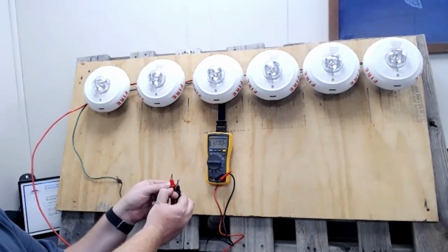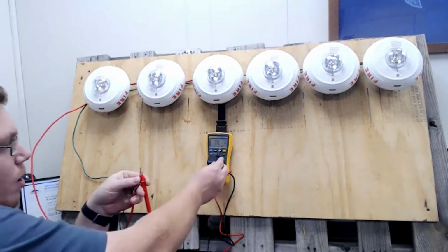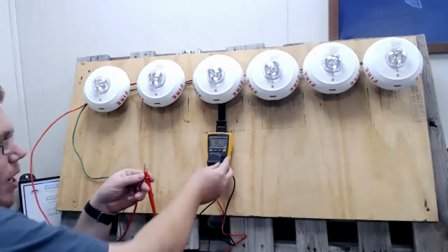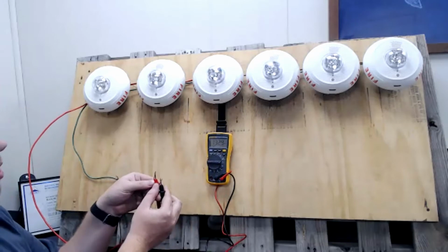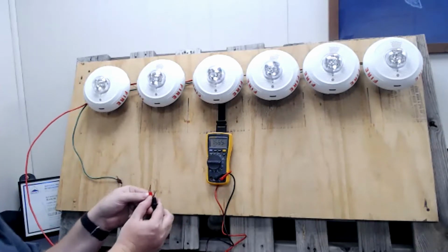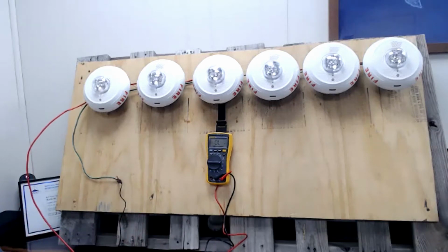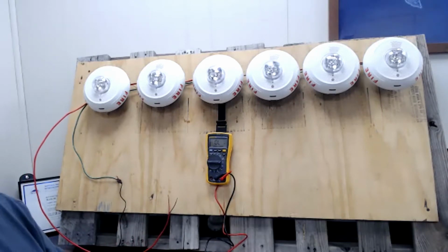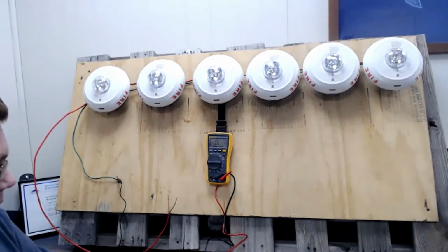So right here, looking at these, I'm bouncing around between 1.2 and 1.3 mega ohms. That tells me I've got an open circuit somewhere. Right here, there's an M beside the ohm symbol. I don't know if you can see that on your phones, but it's mega ohms here. And when I'm in the mega ohm range, that's kind of the equivalent of an open circuit.